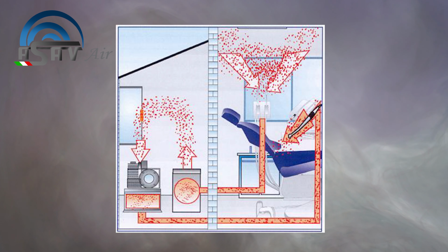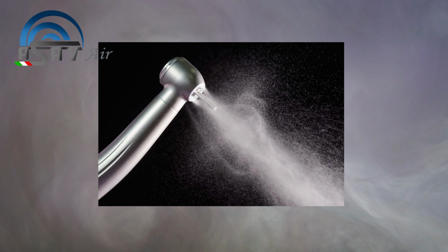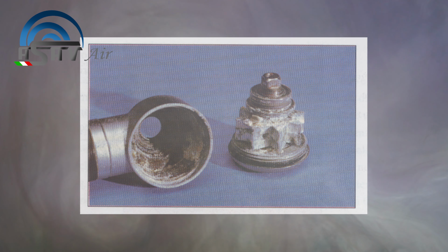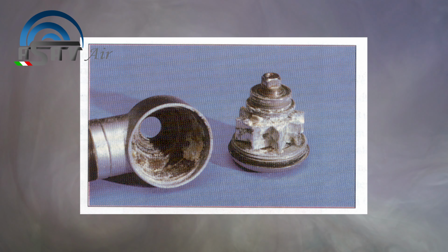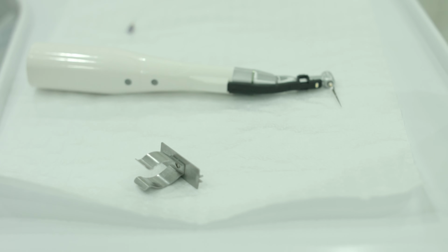Atmospheric air typically contains a percentage of water vapor that can create various problems in the equipment and adversely affect the quality of the final products. Vapors in the airflow can condense in the compressed air system and cause corrosion, fouling, and clogged valves. The presence of moisture in process systems reduces lubrication, leading to the wear of moving mechanical parts, such as turbines.